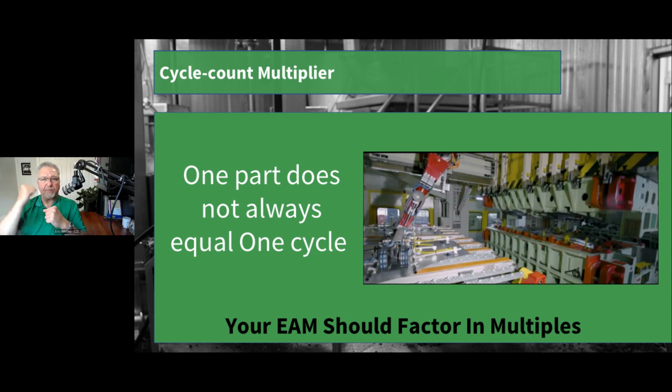Sometimes we can stamp a part, or run a press as an example, and stamp, and it'll make 5 parts. So in production, we want to say for every 5 parts that we produce out in the production side of the world, we want to count 1 cycle over here on this piece of equipment. So make sure that if you're looking at a new CMMS system that does have that cycle-based system, that it has this little feature, because it's a big deal. We call it a cycle count multiplier. So make sure that it has that in there, and that you can actually count that. So that's another big feature that you need when it comes to that cycle-based stuff.